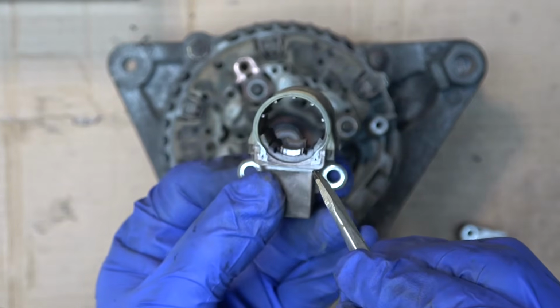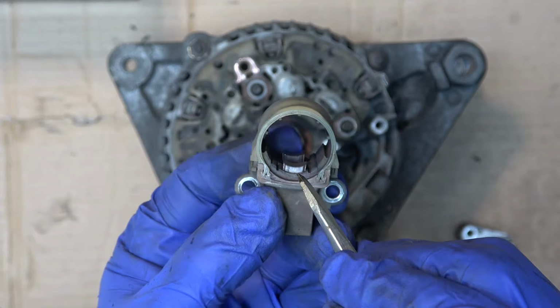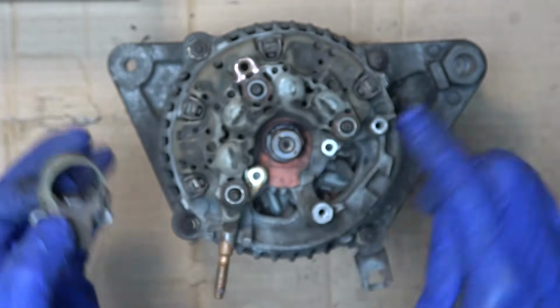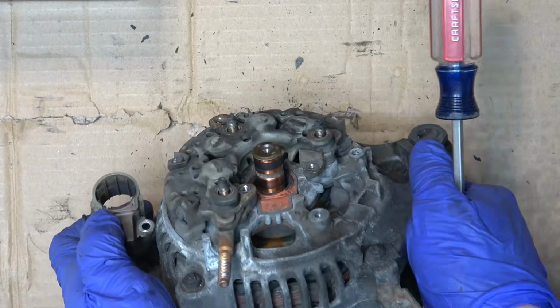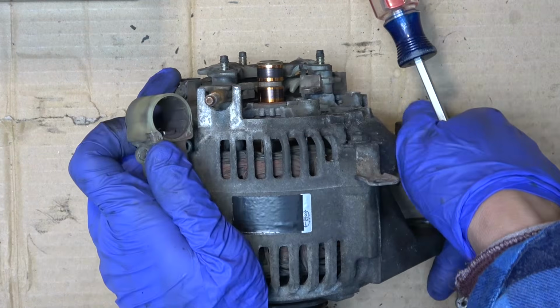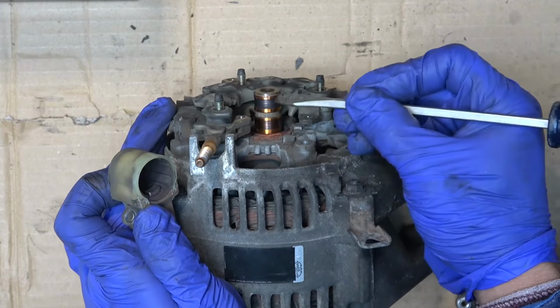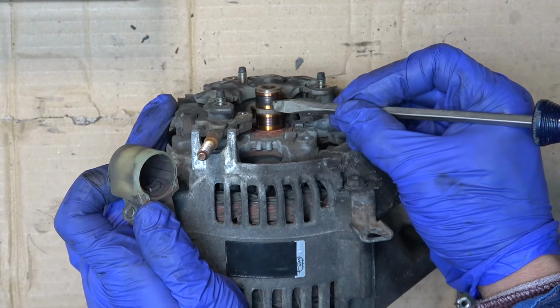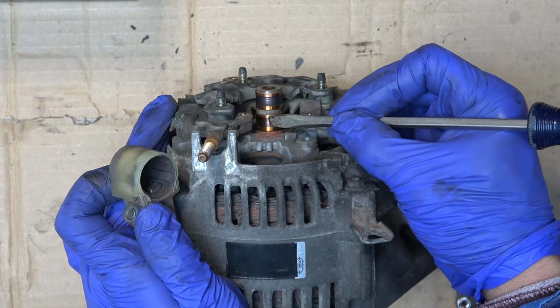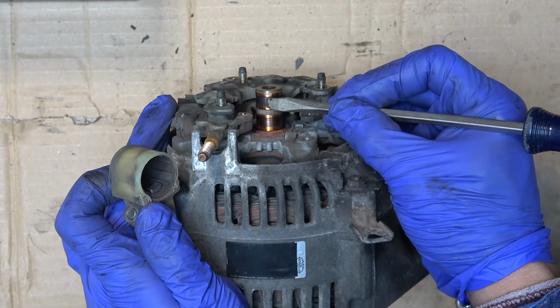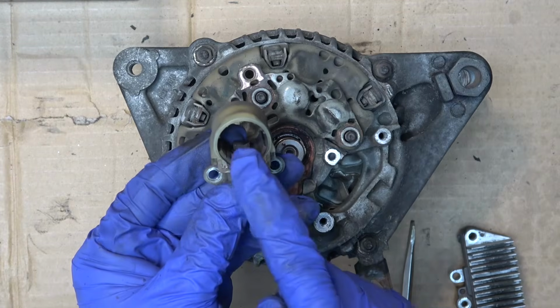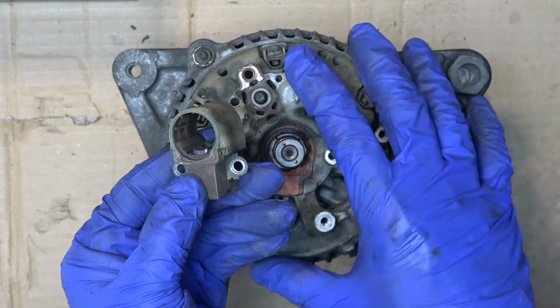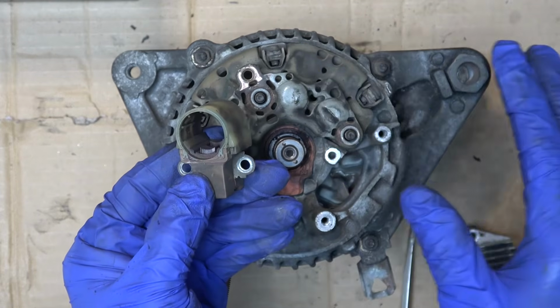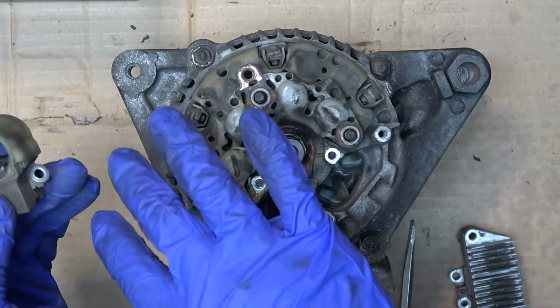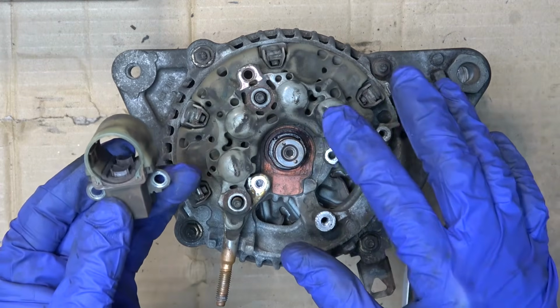The top brush is quite worn, and it's not touching the slip ring on the rotor anymore. Here you can see the two slip rings, one ring on the top, one ring on the bottom, and it's not touching the top slip ring. That, I think, is the problem with this alternator. Could be other problems, I'm going to go ahead and test every single component in a little bit.